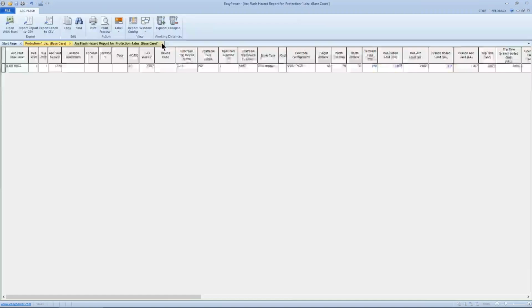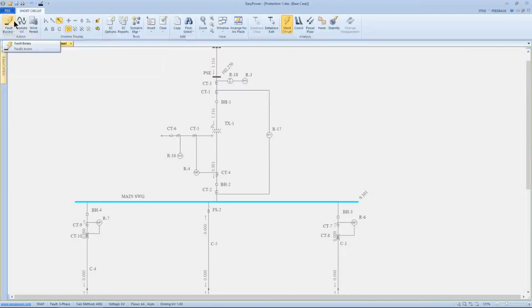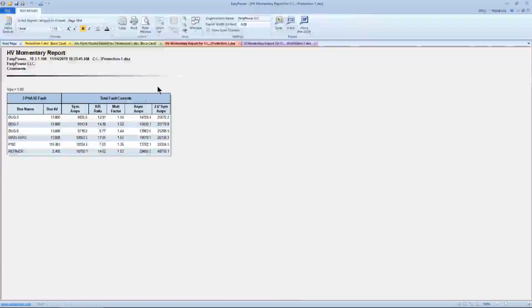If we go back and have a multi-bus fault, we see both high voltage, and I want to make sure I fault all of them. Here again, I'm reemphasizing the point that the tool is calculating the X over R at each bus. This gives us the ability to comply with, or at least have a comparison between, the asymmetric and the 2.6 times the symmetric value that's prescribed by the standards, and how that compares to what the manufacturer has provided on the data sheet.